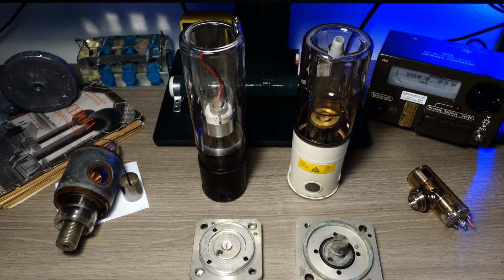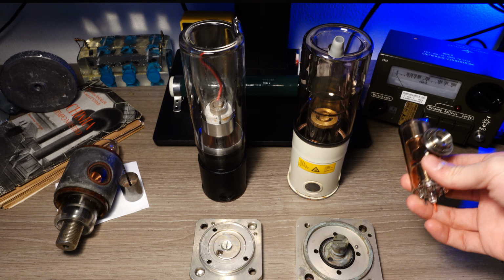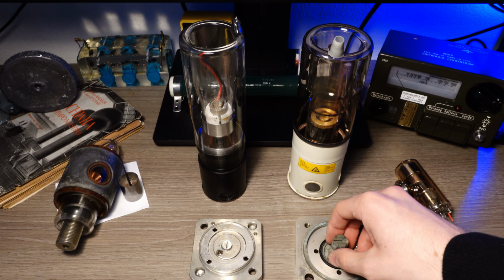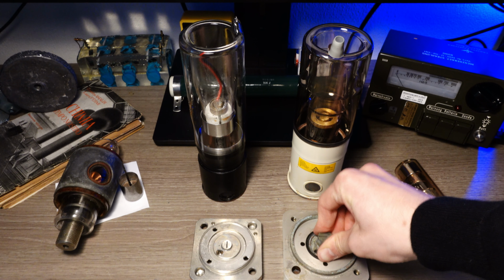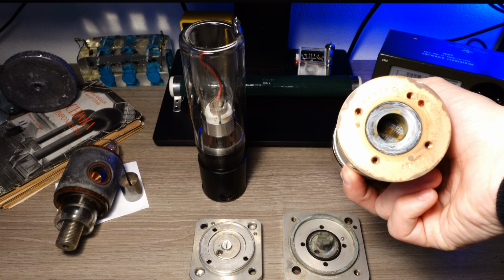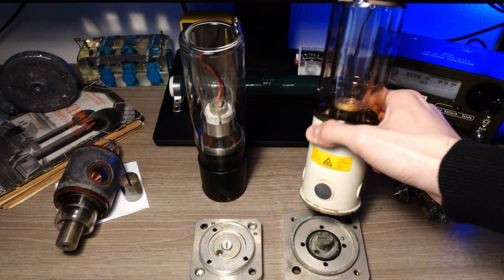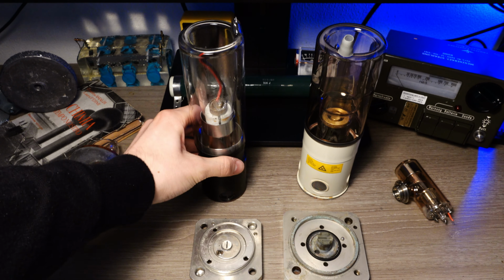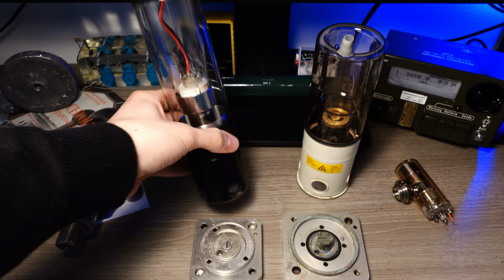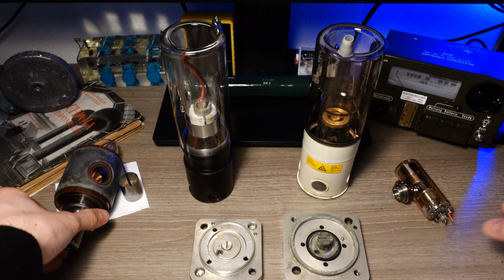But anyway, compared to, for example, a dental X-ray tube, it's a lot easier to get higher damage with this kind of tube, due to the fact that an accurate dose is harder to calculate, as low energy X-rays cannot be detected with most normal instruments, because they can also be absorbed by the probe itself. So you need something like an ionization chamber or a proportional detector that is capable of reaching the lowest range to be able to measure an accurate dose.